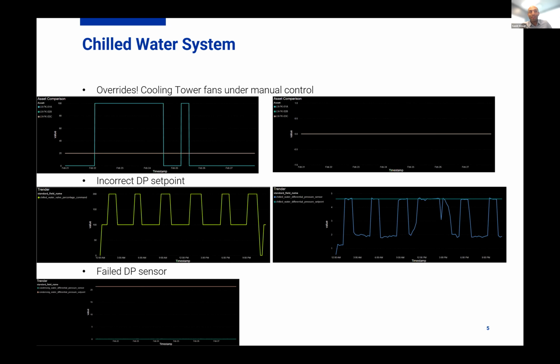And the only way we realized this was that we were looking at our valve operation and it didn't make sense. It wasn't lining up. It wasn't being as efficient. And after a couple of rounds of meetings and talking with people and trying to figure out, what we found out is that, yeah, they just miscommunicated with each other. And this was one of our biggest issues. And the last item was a failed differential pressure sensor. So this is, again, a brand new building, fully commissioned, but one of our sensors had failed. And we had our 2 chilled water pumps running at 100% all the time until that got replaced.